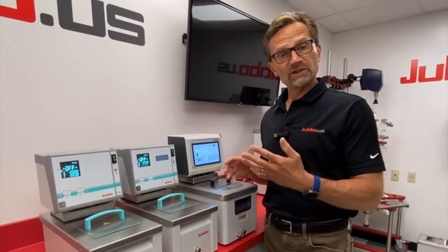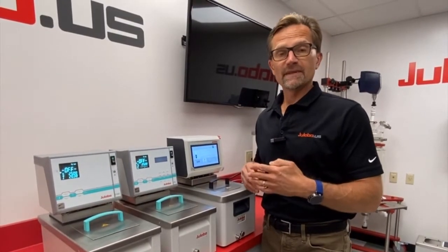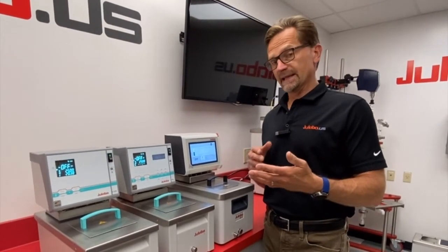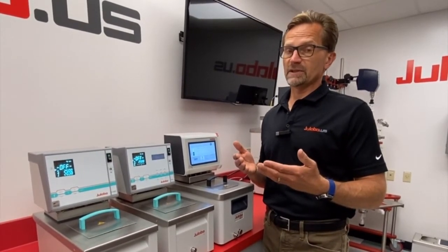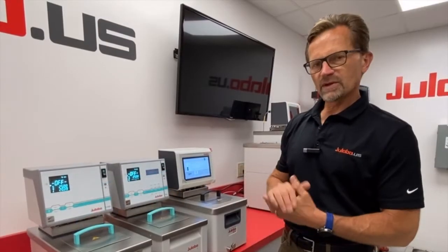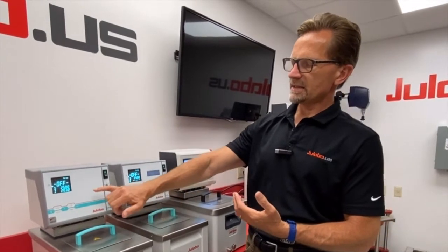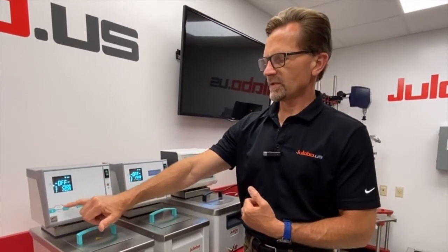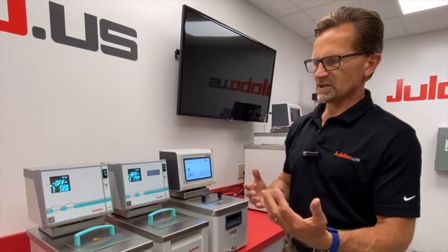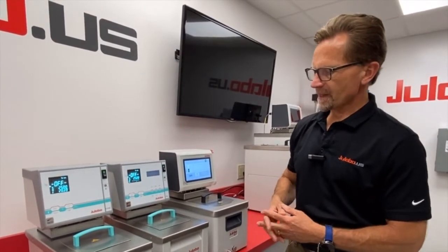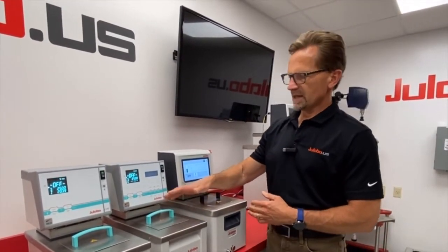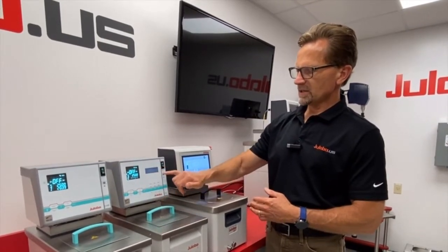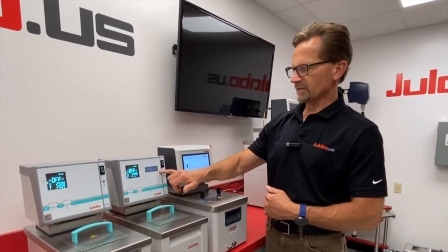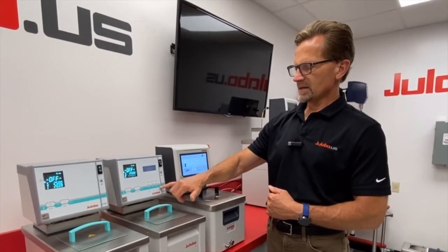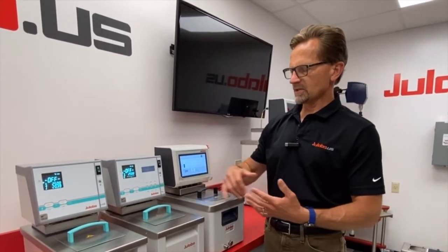They come with a pressure suction pump with 4 speeds. The pressure range is from 5.8 to 10.2 psi on the pressure side with a flow rate of 22 to 26 liters per minute. From a usability perspective, you can see the HE has a TFT screen with buttons for interaction and data entry, changing your settings and things of that nature. If we move over to the HL, you'll see it has the same thing as the HE with the addition of an LCD screen for additional information and a numeric keypad, which makes set point and data entry a lot easier.